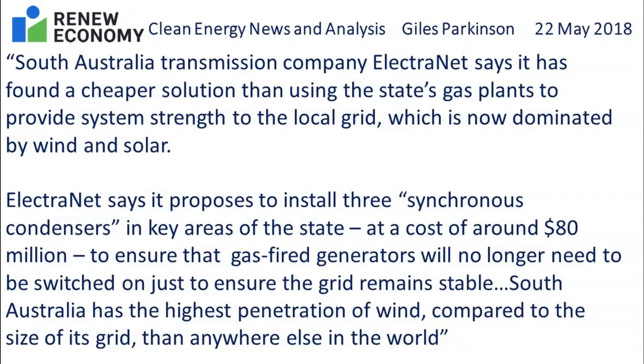We were able to confirm that South Australian Transmission found it cheaper to put in synchronous condensers, the three synchronous condensers we worked on, than providing strength from gas-fired generators. They will no longer be needed to switch on just to ensure the grid remains stable. And as I said before, South Australia has the highest penetration of wind compared with the size of its grid than anywhere else in the world.